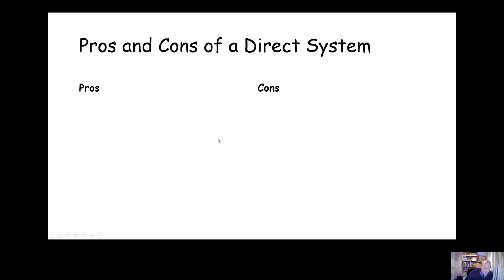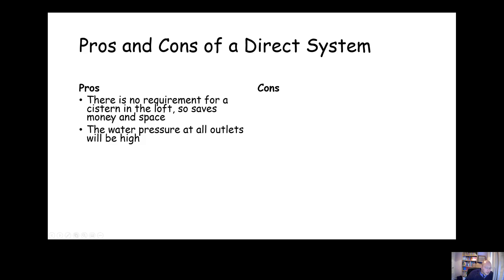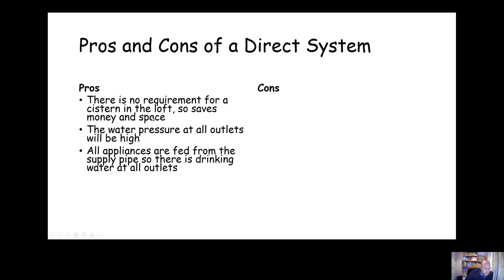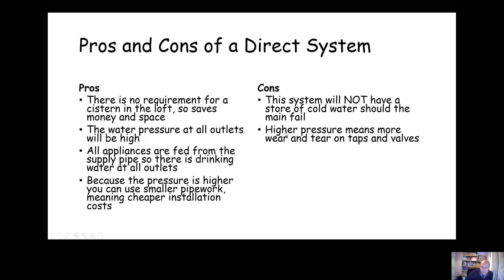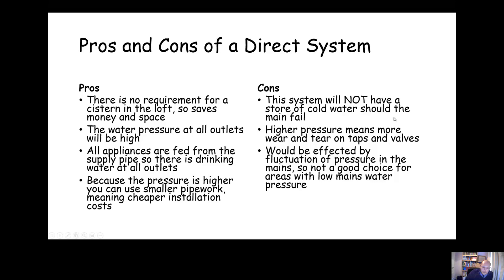The pros of a direct system: no requirement for a storage cistern in the loft, saving money and space. Water pressure at all outlets is high since all appliances are fed from the supply pipe, providing drinking water at all outlets. Higher pressure means smaller pipework can be used, reducing installation costs. The cons: the system will have no store of cold water if the mains fail. Higher pressure means more wear and tear on taps and valves, and the system can be affected by pressure fluctuations on the mains.